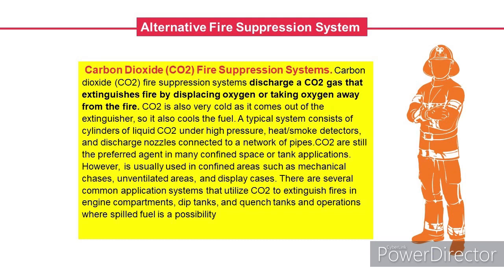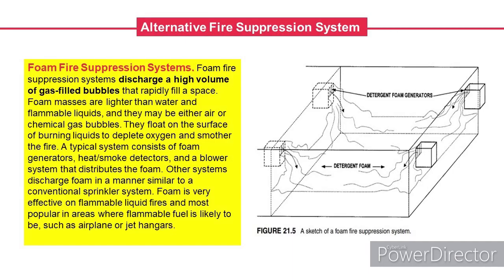There are several common application systems that utilize CO2 to extinguish fires in engine compartments, dip tanks, and quench tanks, and operations where spilled fuel is a possibility. Fourth is the foam fire suppression systems. Foam fire suppression systems discharge a high volume of gas-filled bubbles that rapidly fill a space. Foam masses are lighter than water and flammable liquids, and they may be either air or chemical gas bubbles. They float on the surface of burning liquids to deplete oxygen and smother the fire.